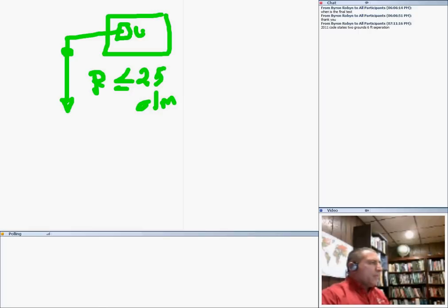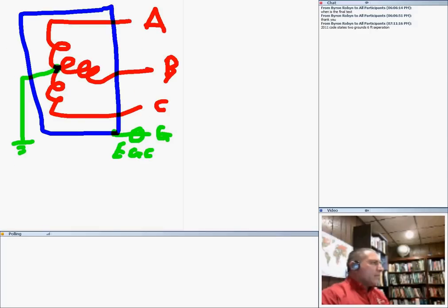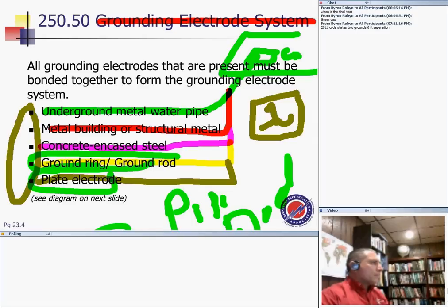So I don't know, how many of you have carried equipment for ground resistance measurement where you can measure it? If you can prove that the resistance is equal to or less than 25, then you don't need another rod or pipe. I don't carry equipment to measure it anyway. If you can't prove it, then you have to go and add another pipe, whether it's residential or commercial. You add the pipe. Any questions, guys? You're off the hook only if you can prove that you can maintain the 25 ohms.